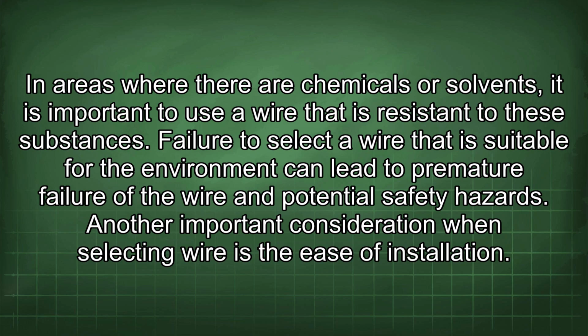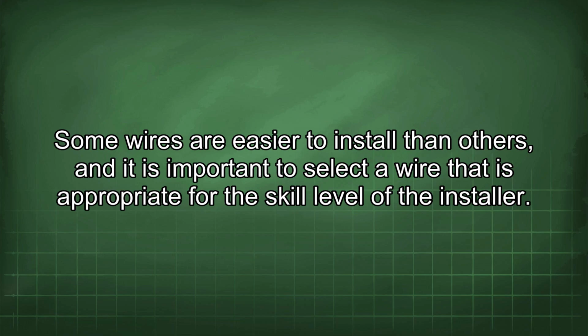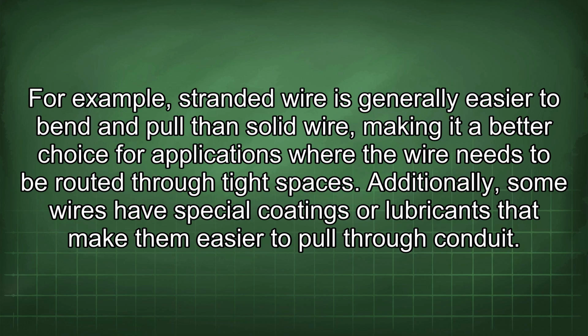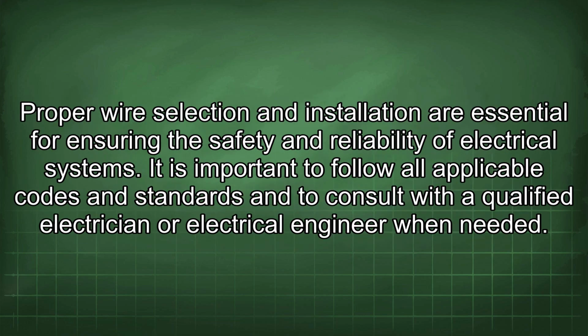and potential safety hazards. Another important consideration when selecting wire is the ease of installation. Some wires are easier to install than others, and it is important to select a wire that is appropriate for the skill level of the installer. For example, stranded wire is generally easier to bend and pull than solid wire, making it a better choice for applications where the wire needs to be routed through tight spaces. Additionally, some wires have special coatings or lubricants that make them easier to pull through conduit. Proper wire selection and installation are essential for ensuring the safety and reliability of electrical systems.